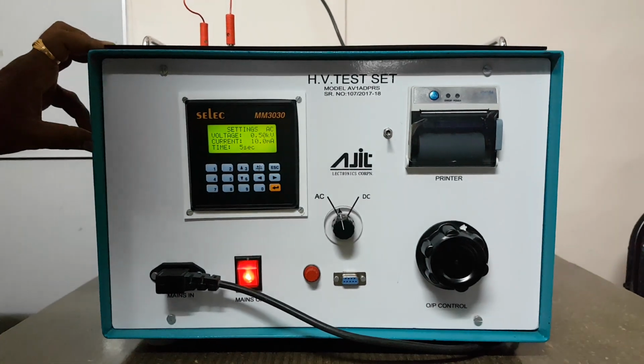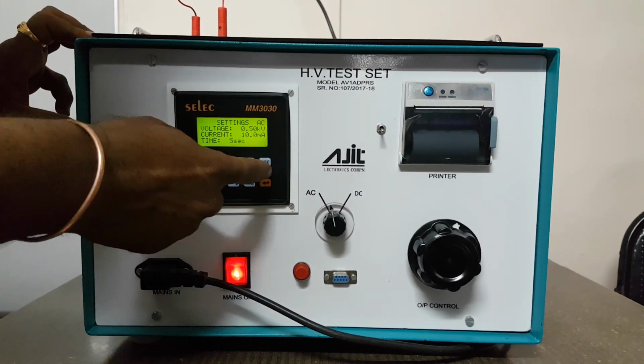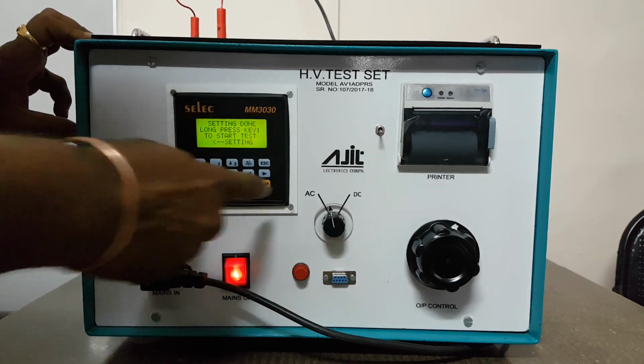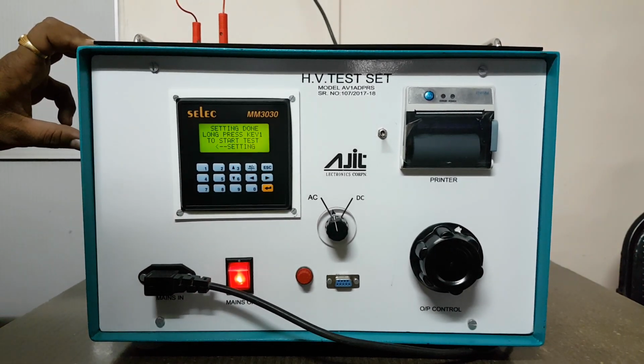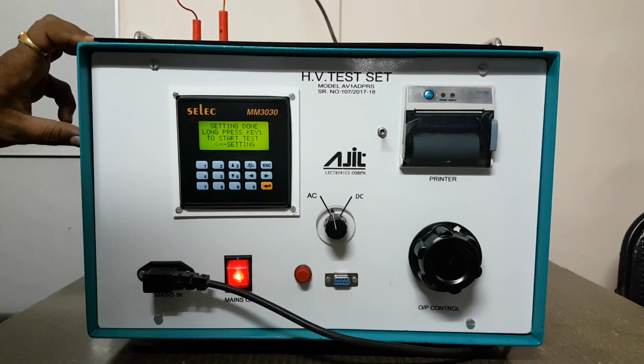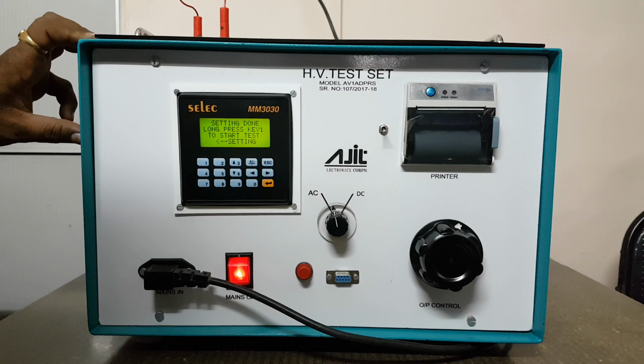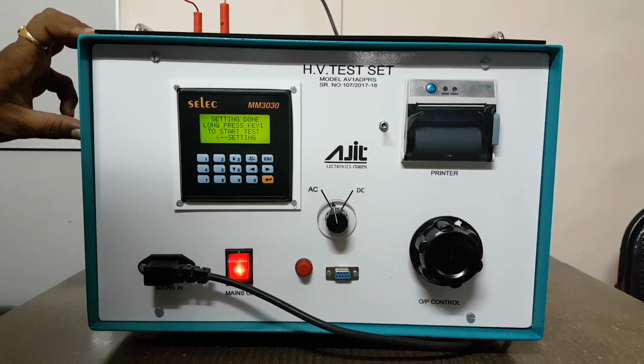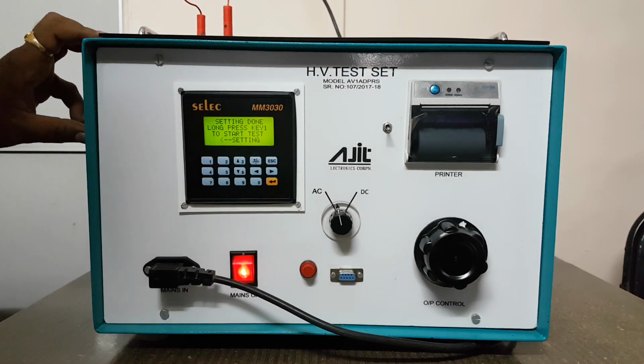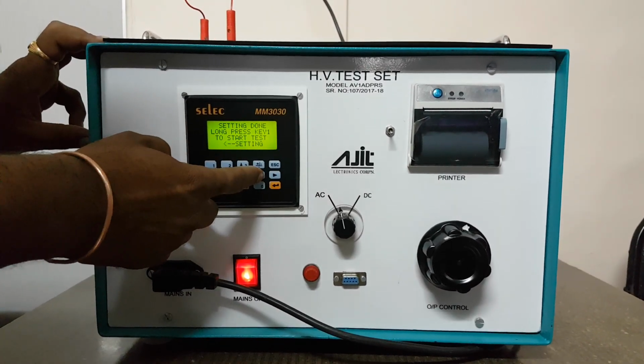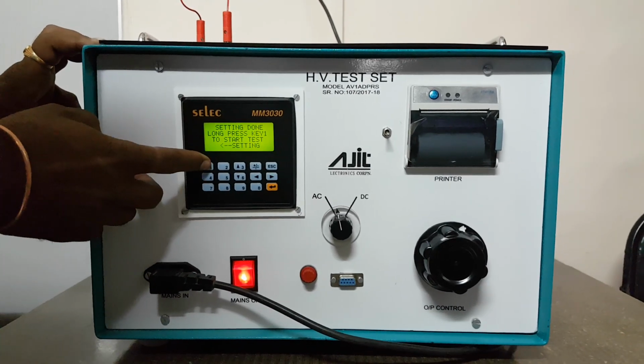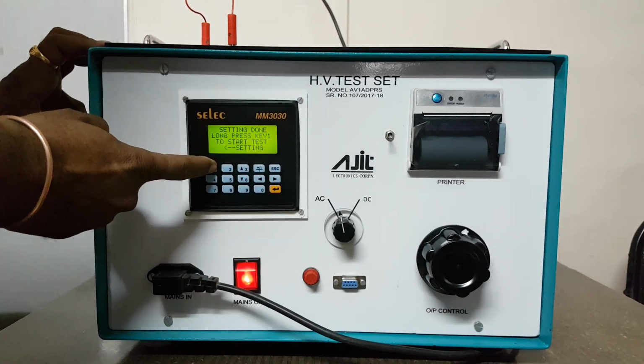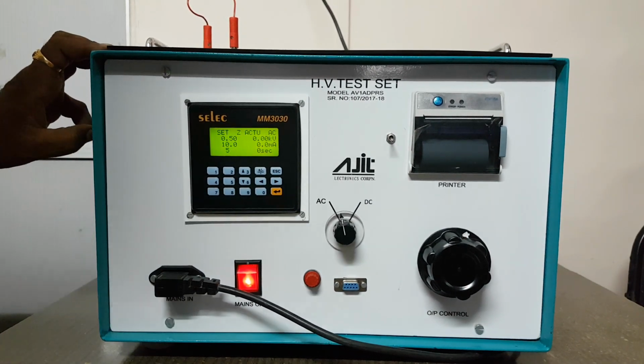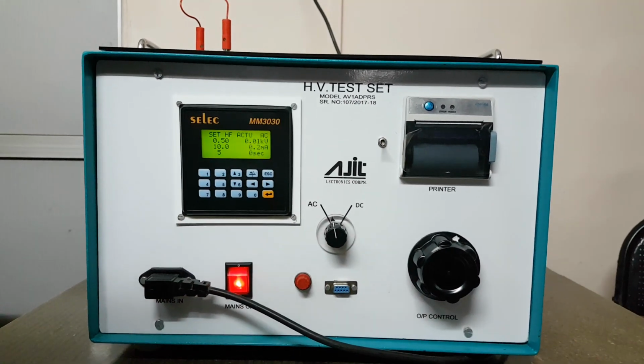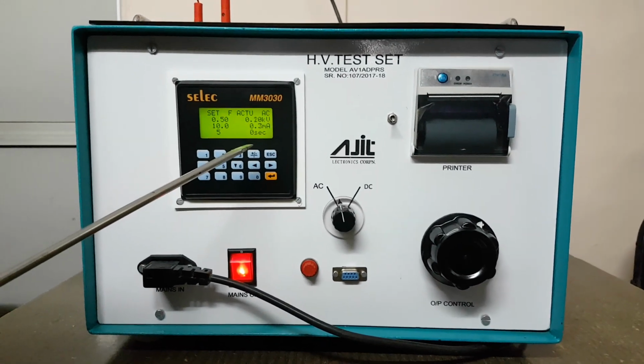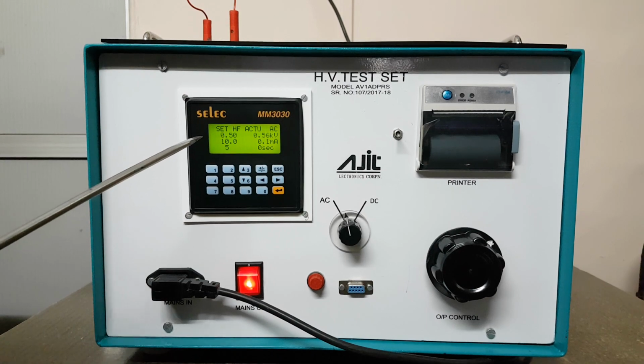Now the instrument has taken all the parameters we have set. For moving further, again press right arrow. The display says settings done. Long press key 1 to start the test. If we want to change the settings, we can go back to the settings with the left arrow. But we want to test, so press key 1 for a long time. Now the testing has started. These are the set values, these are the actual values. H is for high voltage on, F is forward, AC is AC output.